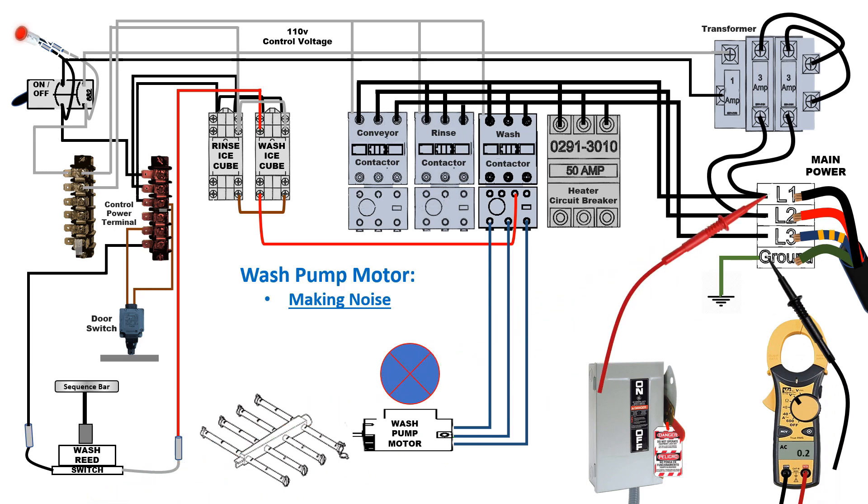Here again, using our multimeter set to AC voltage, one meter lead to ground, we test L1, L2, and L3 at the main power terminal to verify there is no power coming into the machine.